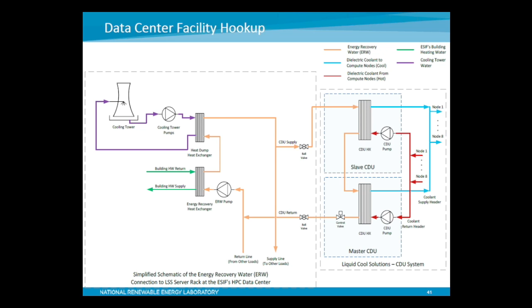The way this data center works is it's a liquid-cooled data center whereby the vast majority of the servers in it are liquid-cooled with an energy recovery water loop shown in orange. That energy recovery water loop, servicing the CDUs of the LiquidCool Solutions system—the cooling distribution units that have the pumps inside—removes the heat from those servers, and then passes it either to the building's heating system, shown in green, or rejects it outside during the summer through the on-site cooling system on the roof of the data center.